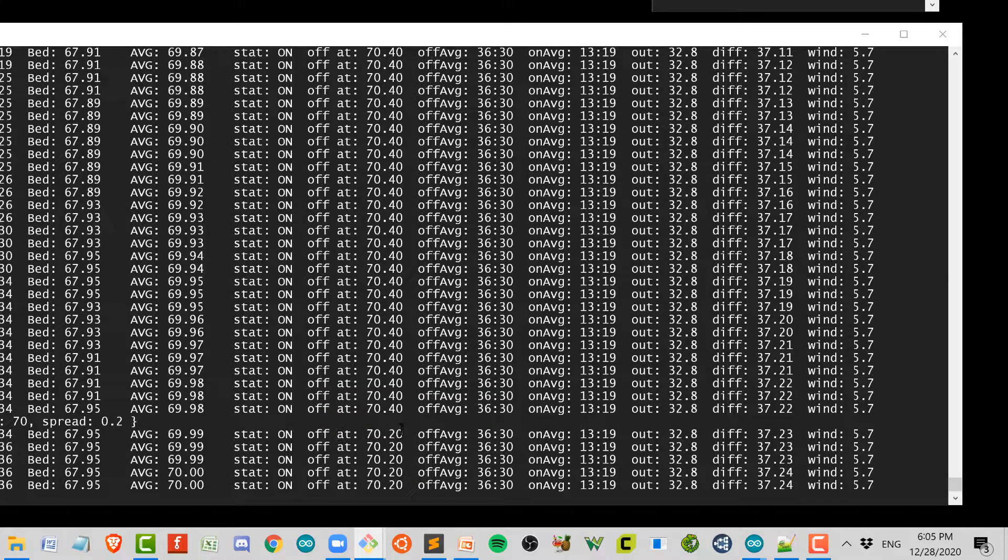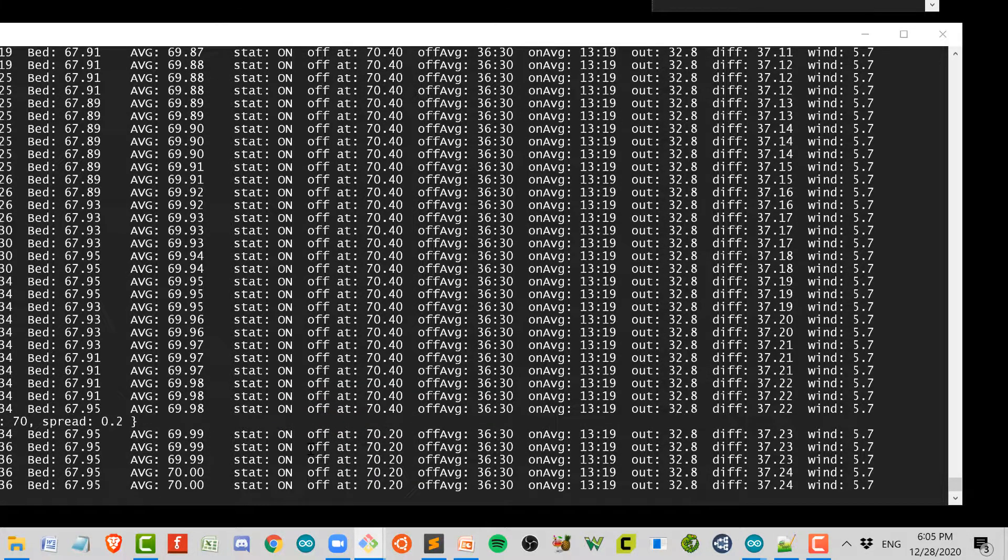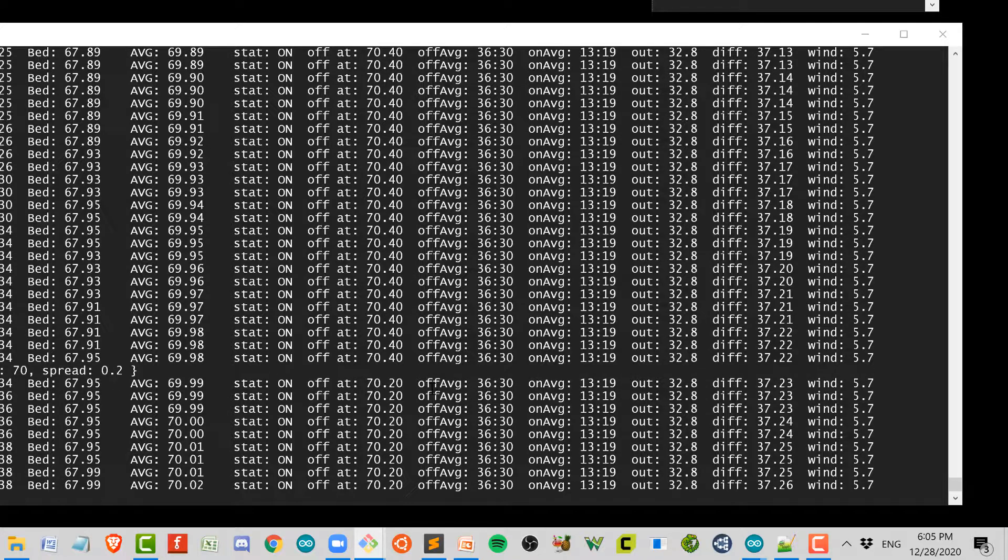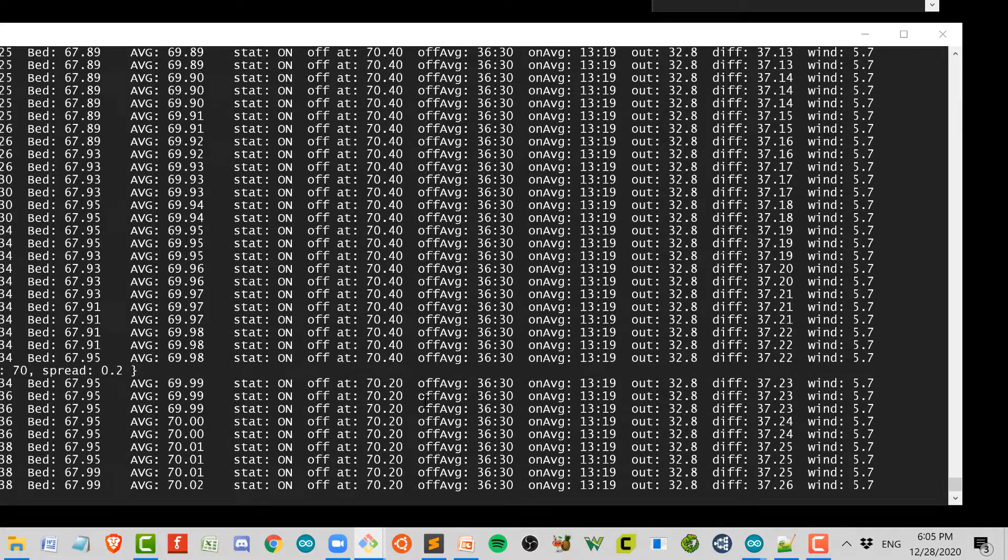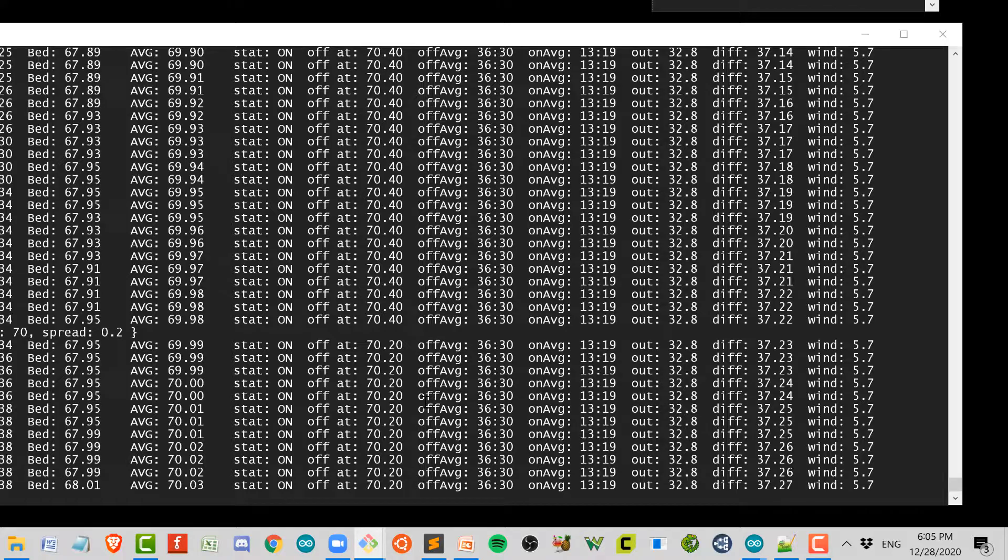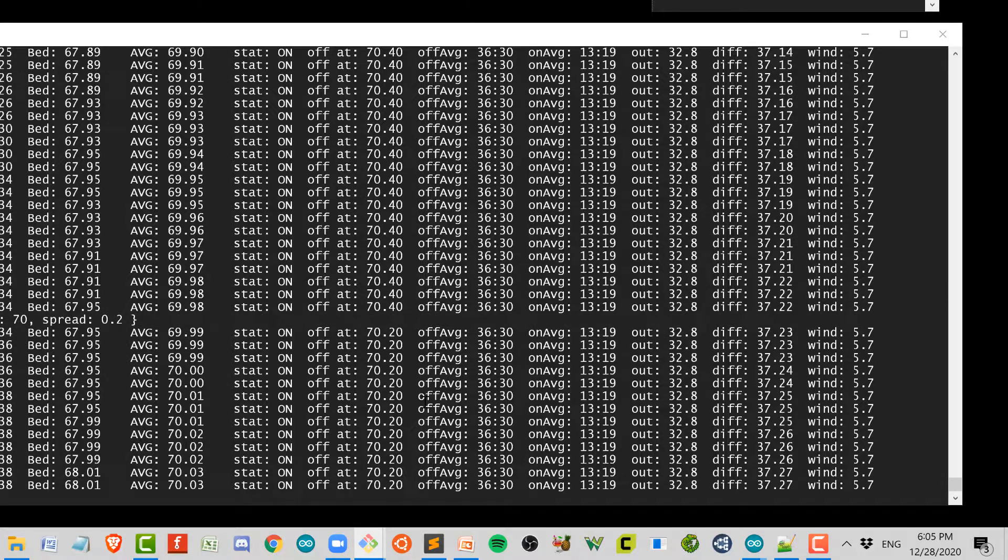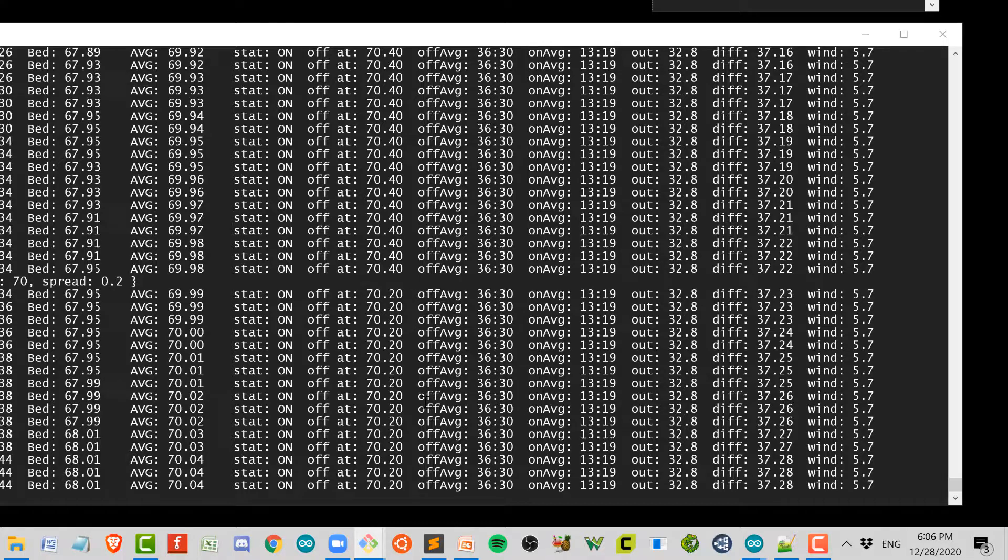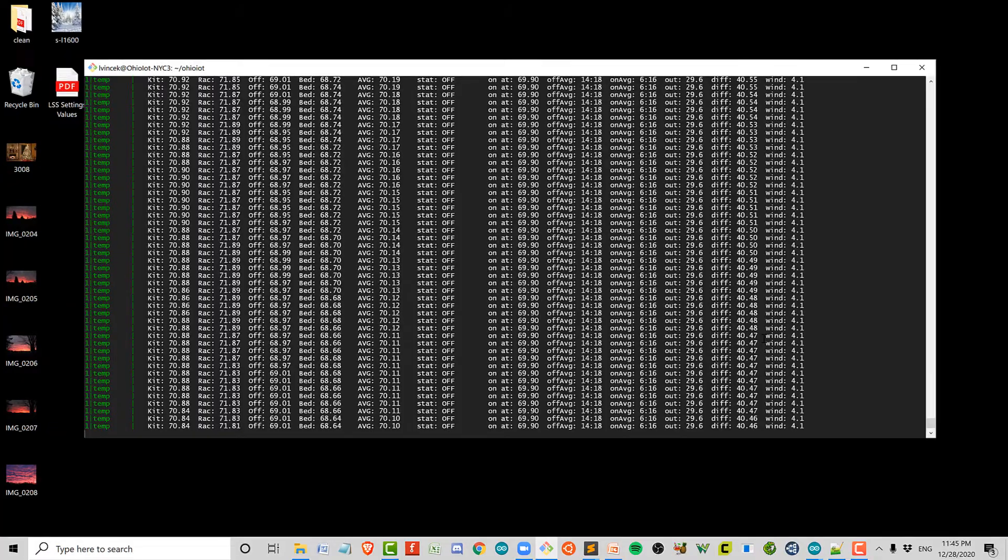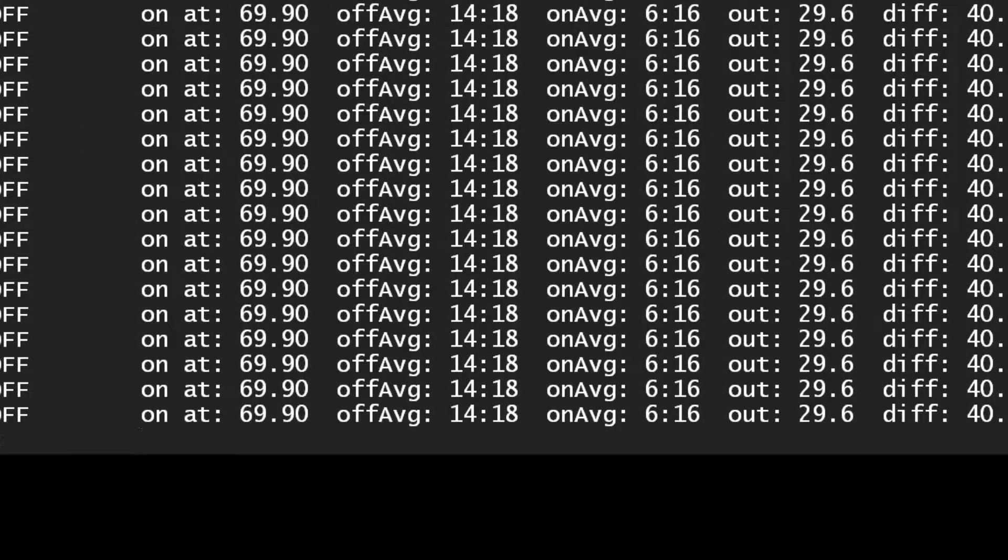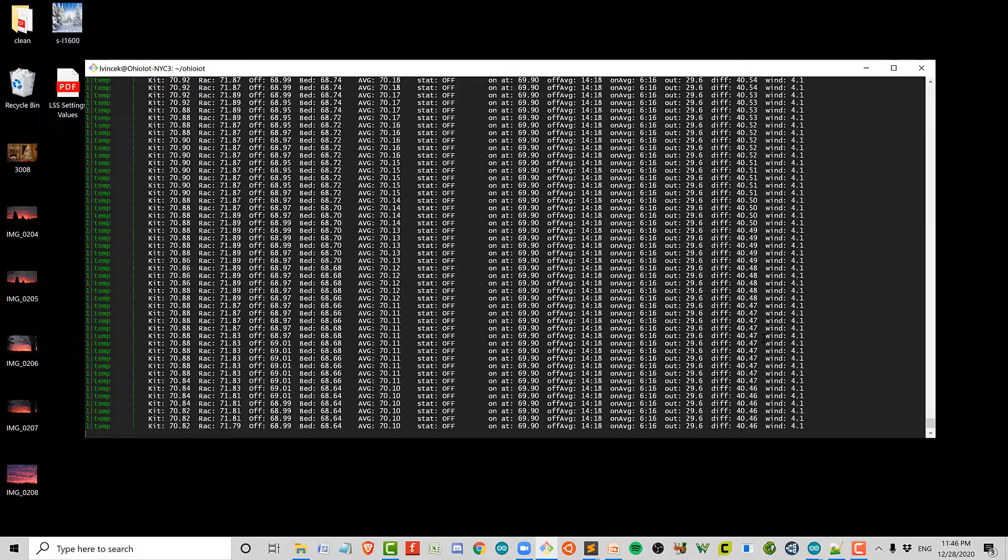Okay, my range is now 69.8 and 70.2, and you can see below that the off at 70.4 changed to off at 70.2. So this got the update. These cycle times are going to come down. Yes, technically I'm probably losing efficiency, but I am gaining comfort and that's what I want right now. I actually like this 0.2 spread. The furnace I believe is still going to be on for about six minutes at a time, but the temperature band in my house is very tight. I'm not cold before it turns on, I'm not hot when it's blowing for too long. It's more comfortable. And there you go, look at the logs a few hours later. We're at six minute on time and 14 minute off time. Maybe not the best use of my furnace, but very comfortable in the house.